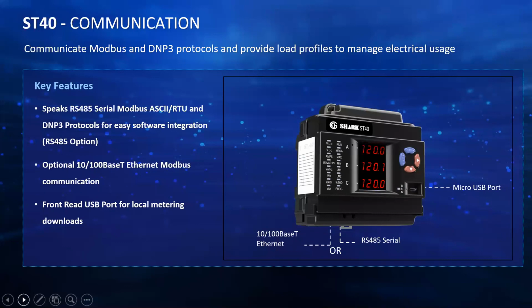For communication options, this comes with 3 different options. So you have a RS485 serial port or an Ethernet port at the bottom of the meter. And then on the front, you also have a micro USB port. So you can use the USB port for local downloads. When you're using the RS485, you can talk to it over Modbus ASCII or Modbus RTU. You can also talk to it over DNP3 protocols for integration into other software.